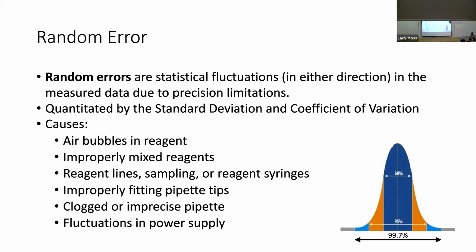So for our purposes, usually we say something is out of control or has failed if it's outside of 2 SD, because that is a good enough cutoff that we're not going to get flags all the time that something's failed, but it also is sensitive enough that we're going to catch something that's gone wrong. You don't want to have to troubleshoot everything all the time. No, you do not have time for that. So you want to be like, okay, something has actually gone wrong without having to go through way too many things. And then you have coefficient of variation, which just normalizes to the mean. So you can look at apples and oranges together, so they both look like watermelons. Essentially, you just normalize to the mean.